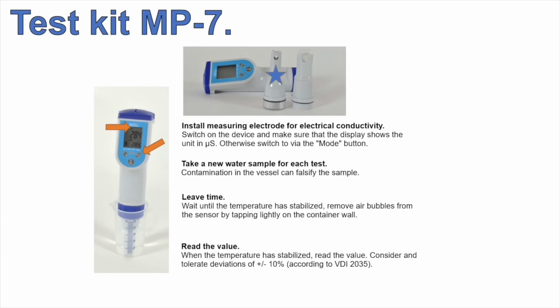Take a new water sample for each test. Contamination in the vessel can falsify the sample. Leave time. Wait until the temperature is stabilised. Remove air bubbles from the sensor by tapping lightly on the container wall. Read the value. When the temperature is stabilised, read the value. Consider the tolerance of plus or minus 10%.